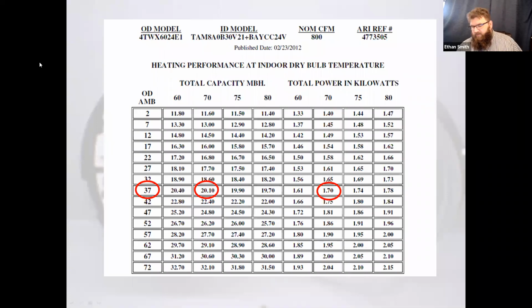Using this same unit, if we were to do that COP at 17 degrees, we would say up here we've got 16,300 divided by 1,540 times 3.41. Anyone getting there faster than me? Do my math. So my bottom number: 1,540 times 3.41 is equal to 5,251. So we go 16,300 divided by 5,251. And I end up with a COP of 3.1 on this unit.